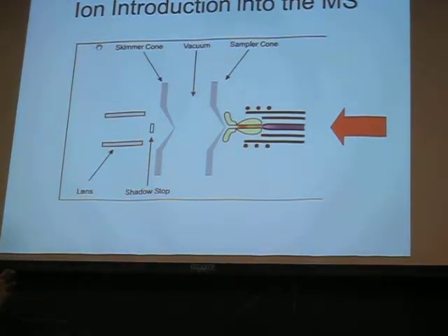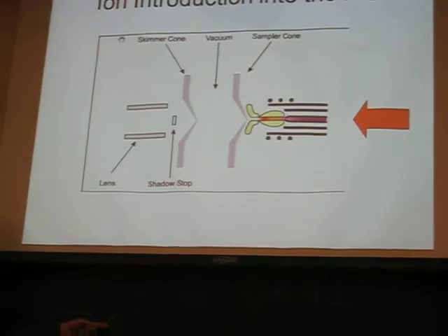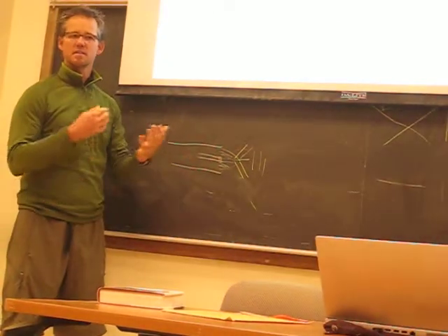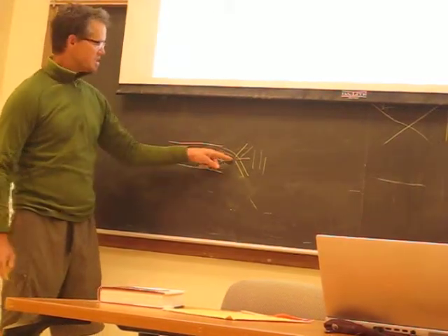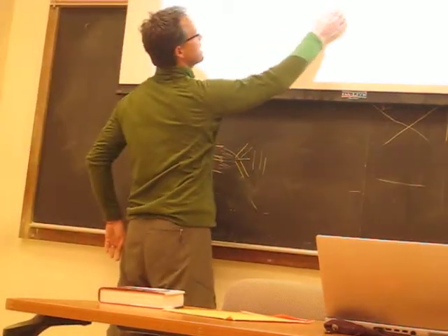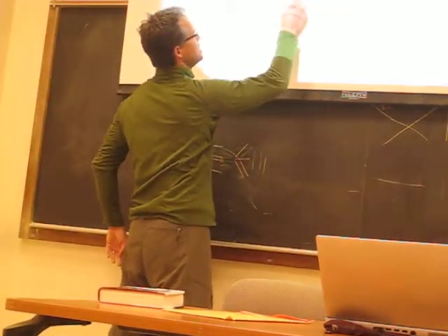One of the challenges with the ICP mass spectrometers was that you needed to generate a very high vacuum, but you need to have a hole in it so your sample can get in. Those are sort of contradicting one another. They solved that by having multiple vacuum stages in the instrument.